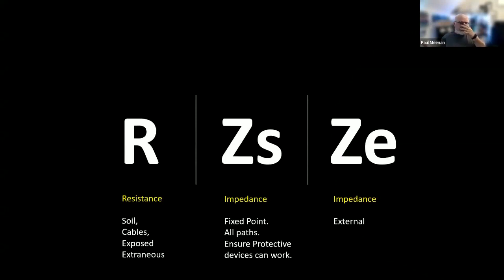Once we have those resistances checked and we energize our systems, we then look at impedance. Impedance being the sum total of resistances at a point. It's a fixed point. So you go to a socket, a light, a fuse box, and it does a test. It checks the resistance of all paths of resistance. And we want nice low impedances, because if we have low impedance, we then have lots of energy flowing to activate our protective devices.